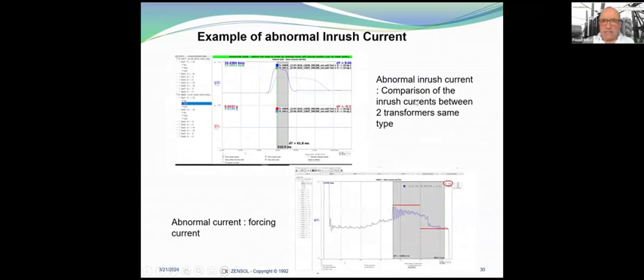Here you can see an abnormal in-rush current. Here you can see one which is normal and the other one which is flat, which is not normal, and that creates problems with the breakers, so the breaker operates. This is just a bad adjustment of a timer inside the control cabinet. This test has been done on a totally new transformer with a tap changer.